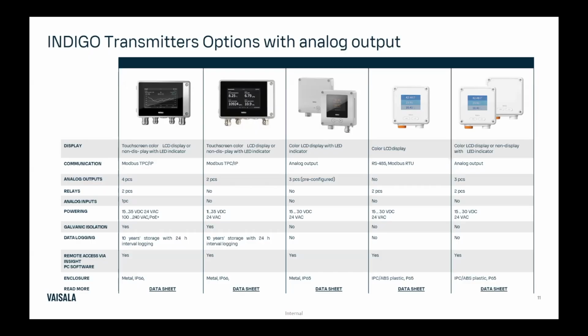So over on the left, we'll see two that look pretty similar. That's our Indigo 500 series. The left being the 520 and the 510 being what we call the little brother. So the Indigo 510 supports one probe. It does have a touchscreen display, and you can configure any analog outputs, any settings through that display. It would not be pre-configured from the factory. Along with that, you get an Ethernet connection that supports transmission of data through Modbus TCP/IP, as well as internal data logging that can be accessed through that remote web interface through that Ethernet connection.